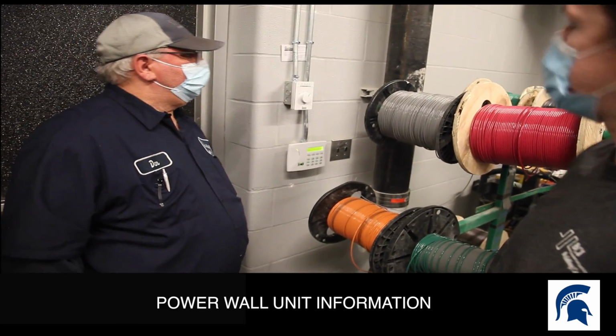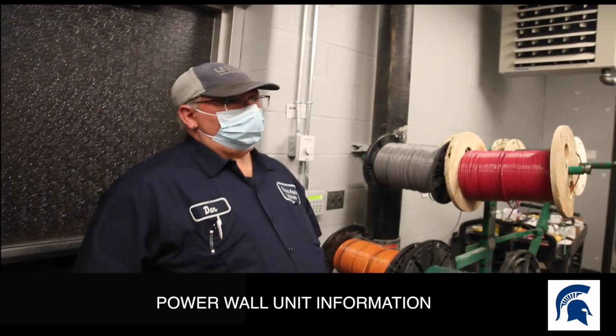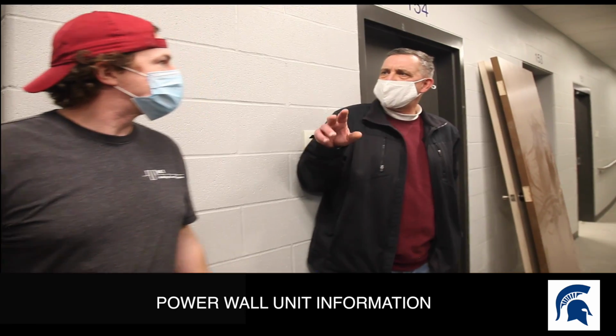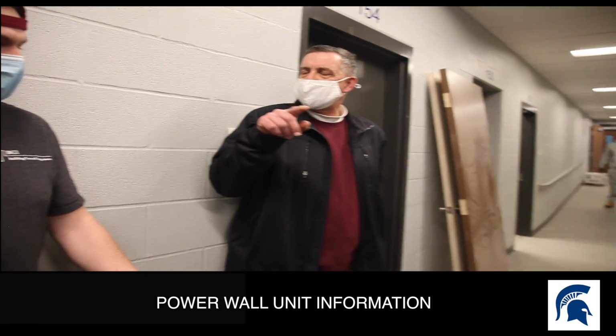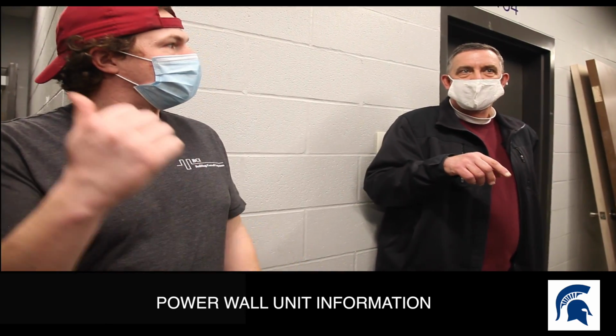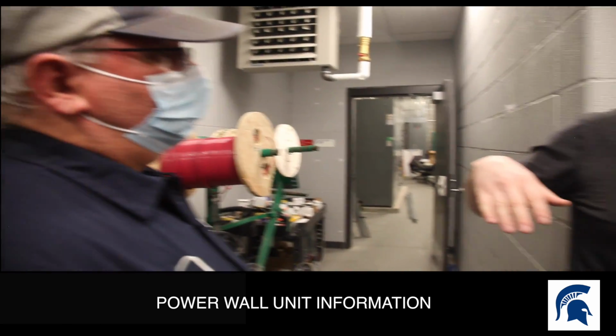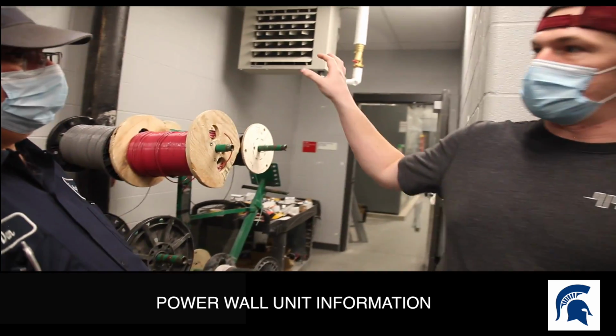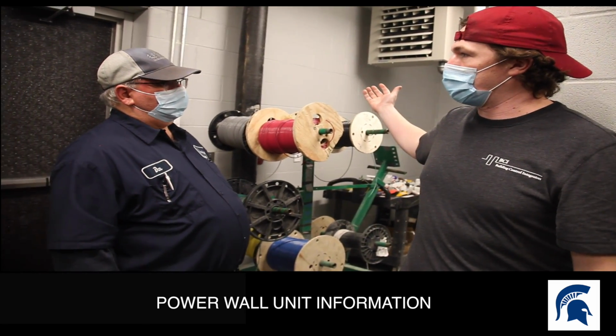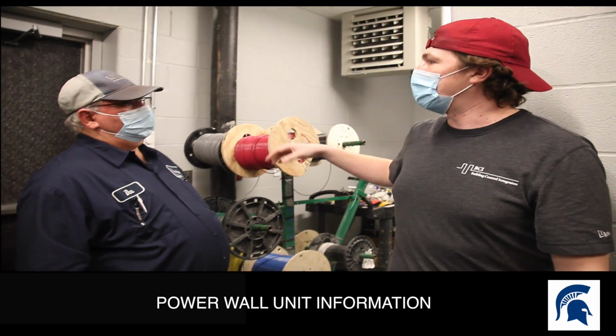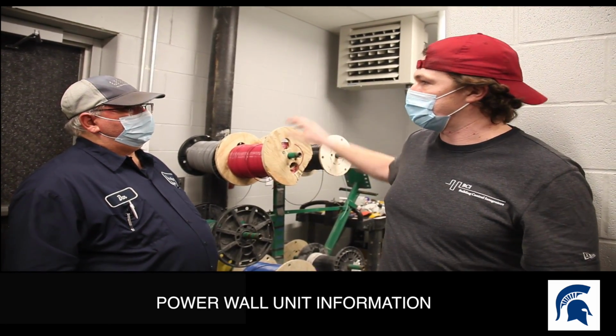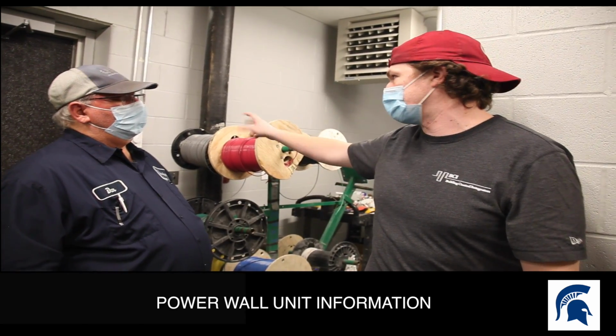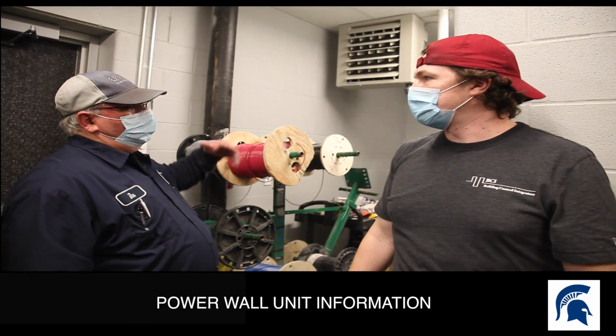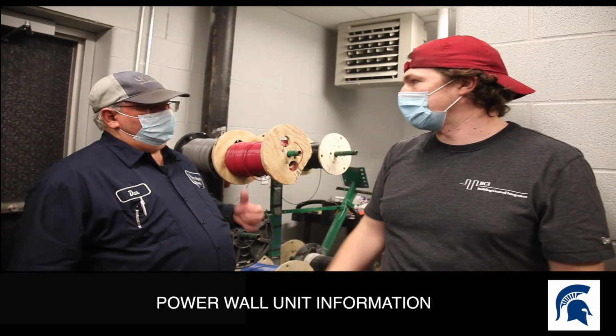Sounds good. And all your cabinet heaters too. Cabinet heaters are controlled through the computer, right? So all of these, when it's below 55 degrees, and that's adjustable, the power will be enabled so you can use them. But over 55 degrees, all these will just be disabled. Well, if it's 55 outside, you can do whatever you want. It's not going to kick on. Under 55, they'll be enabled.